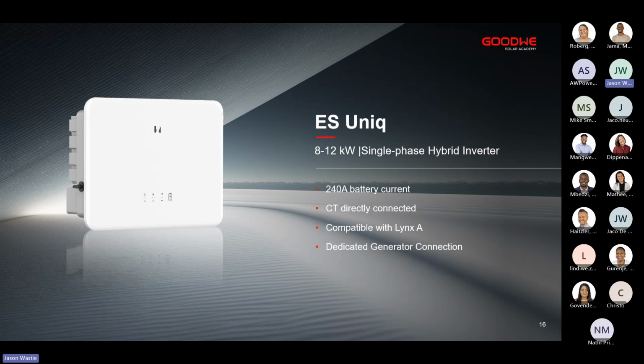CT directly connected. So what this means is that a smart meter is not needed. It is built in, so long as the CT is connected within 10 meters; a smart meter will be needed if the CT is connected more than 10 meters away. The ES Uniq is compatible with the Goodwe Lynx A battery and many more. These inverters are now also equipped with a dedicated generator port, which will be doubled up as a big load AC output.